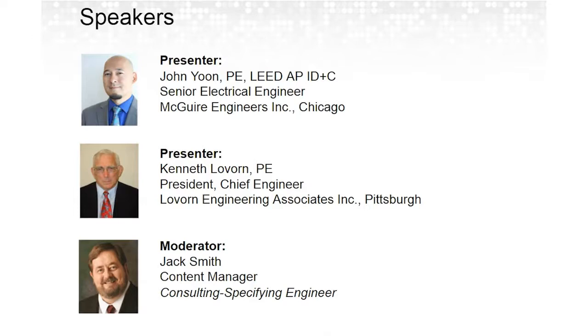Are VFDs worth installing for constant torque load, and will there be any significant savings? That's a good question. For constant torque loads where the motor is significantly larger than the load, then I think using a VFD on a constant torque load is really a good application. But let's say, for instance, you have a motor that's 10% or 5% larger than the total load on the system. You may have trouble paying for the VFD if you only have 5 to 10% savings, since the savings is linear.